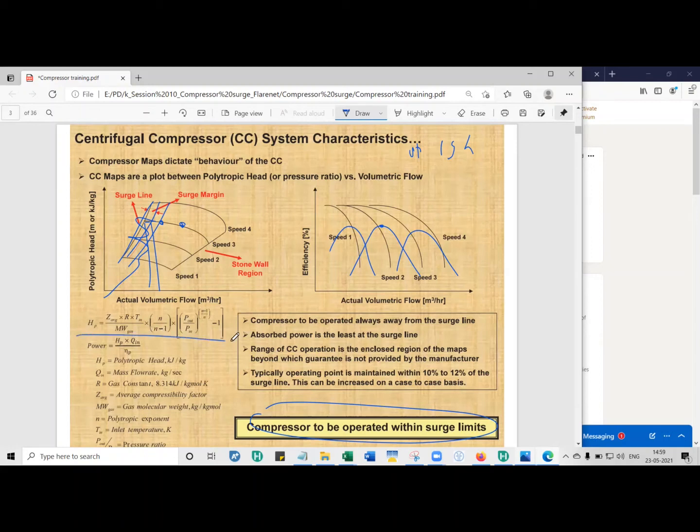As shown here with these two expressions, what we are doing is taking into account the changes in density through the gas compressibility factor, the inlet temperature, molecular weight, polytropic exponent, and the pressure ratio.